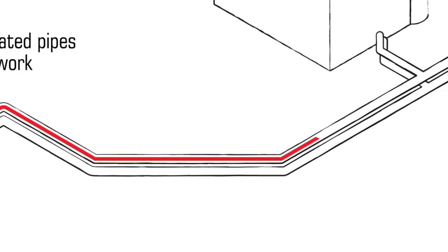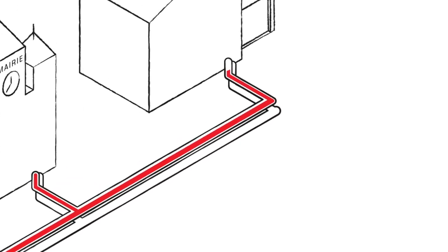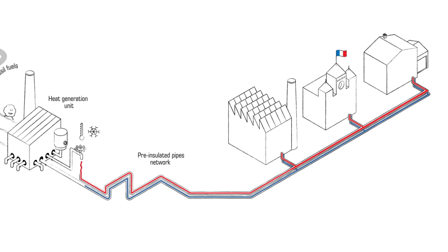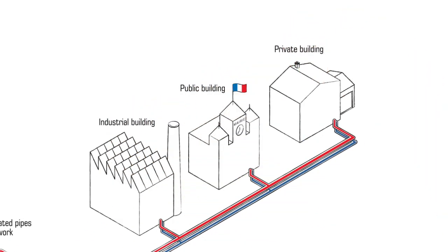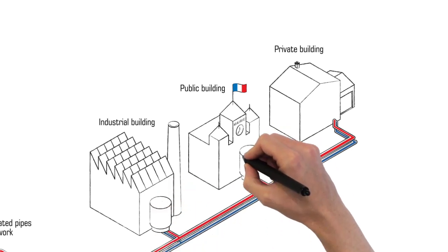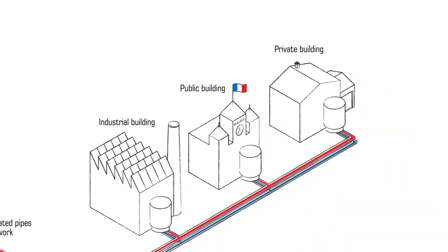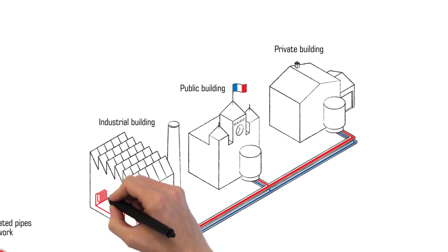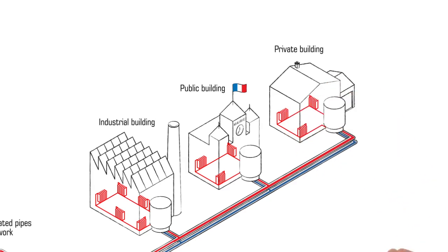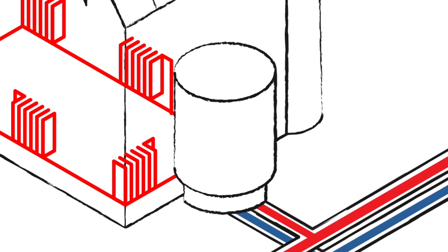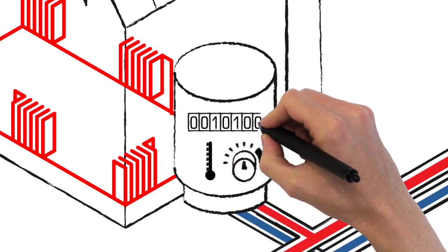This water is then channeled by the network of pre-insulated pipes to the various places of consumption, which are industrial, public or private buildings. Within every building, substations are equipped with an exchanger. They help transfer heat from this network of pre-insulated pipes to the internal network of the buildings. The exchanger also gives the possibility to adjust the flow and the temperature to users' needs and to account for their heat consumption.